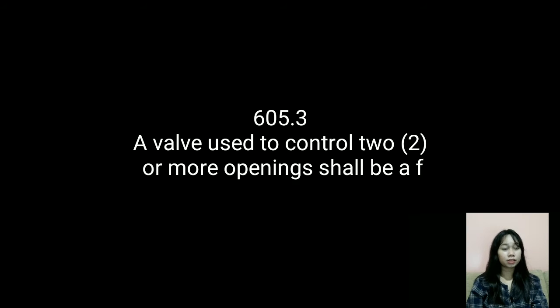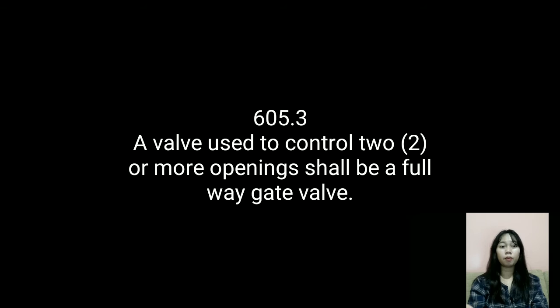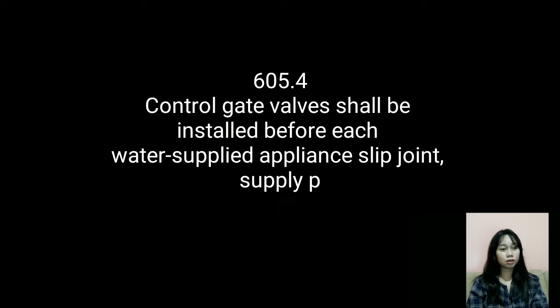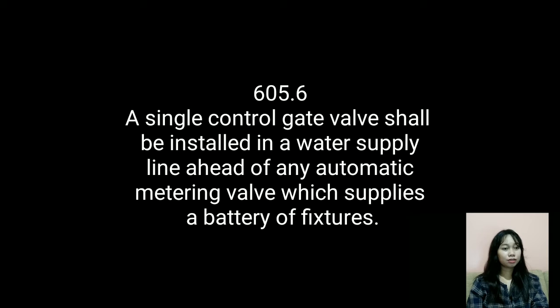In Section 605.3, a valve used to control two or more openings shall be a full-way gate valve. In Section 605.4, a control gate valve shall be installed before each water-supplied appliance and slip-joint supply pipings for non-metallic fixtures. In Section 605.5, all required shut-off or control valves shall be accessible in all buildings. In Section 605.6, a single control gate valve shall be installed in a water supply line ahead of an automatic metering valve which supplies a battery of fixtures.